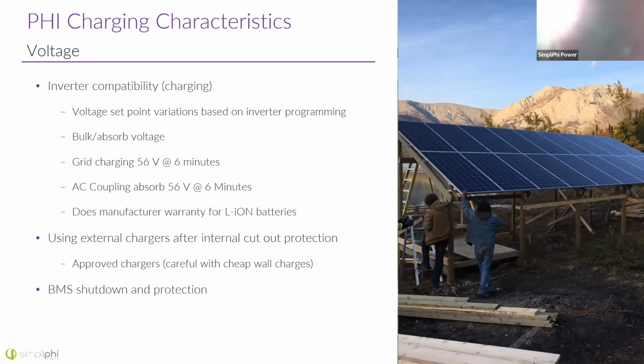For AC coupling, we're going to absorb at 56 volts for 6 minutes. For grid charging, also the same thing, 56 volts for 6 minutes. Sometimes if you're setting in terms of an hour, that's 1/10 of an hour. And if you're trying to check to see if the charge controller is going to work, make sure that the manufacturer warranties it for lithium-ion batteries. Maybe the system was just so old that it was designed only for lead acid and it doesn't have the appropriate set point for lithium-ion batteries. You'll save money in the long run. Batteries are expensive, so first upgrade the equipment and then install lithium-ion batteries.